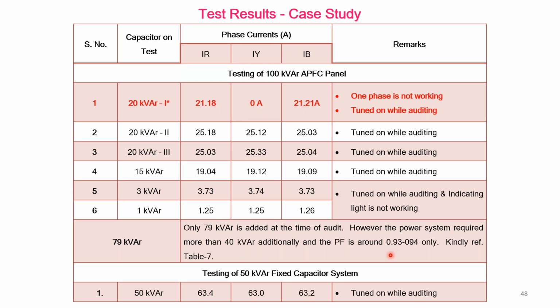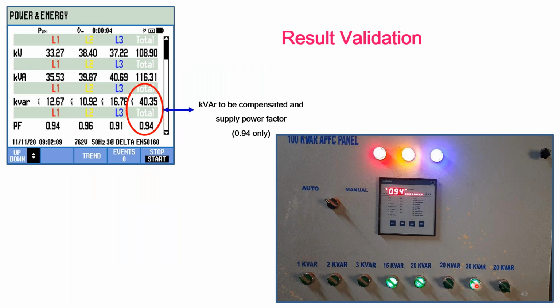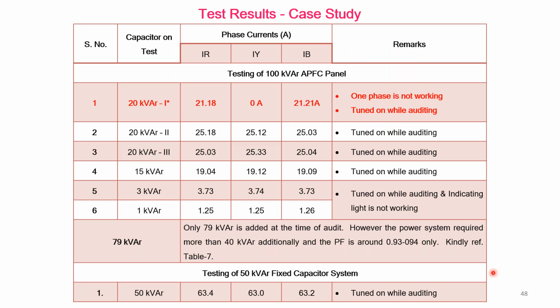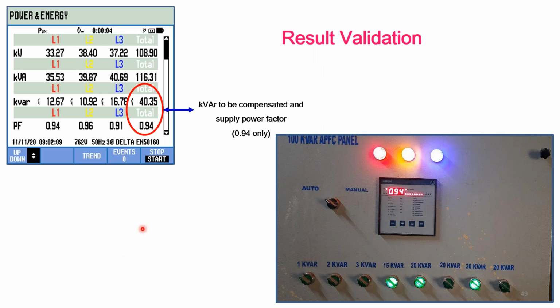But keep in mind that some of the capacitors are on, but the light is not on. See, this is on. 20 kVA is on, but the light is not. This is because of the fault in the light system. Even though out of 100 kVA only 79 kVA is turned on, the power factor at the supply side is going to be 0.94. Still reactive power is available to compensate.